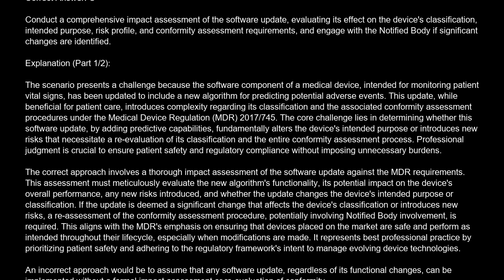If the update is deemed a significant change that affects the device's classification or introduces new risks, a reassessment of the conformity assessment procedure, potentially involving notified body involvement, is required. This aligns with the MDR's emphasis on ensuring that devices placed on the market are safe and perform as intended throughout their life cycle, especially when modifications are made. It represents best professional practice by prioritizing patient safety and adhering to the regulatory framework's intent to manage evolving device technologies.